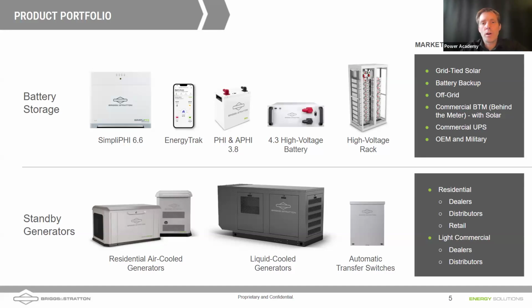It's also notable that our batteries, we do make a 24-volt battery still. There aren't a whole lot of manufacturers that are doing that. That's the 24-volt PHI battery produced in Oxnard, California. And then both the PHI and the SimpliPHI and the 6.6 have 48-volt options, which is a lower voltage option, which offers a little bit less restrictions on installation, etc., for batteries under 60 volts.